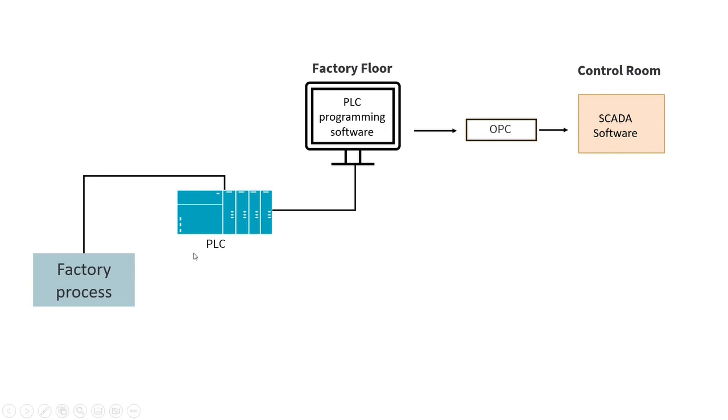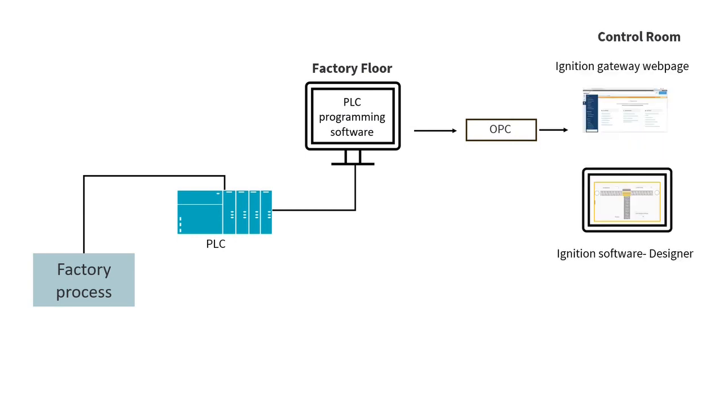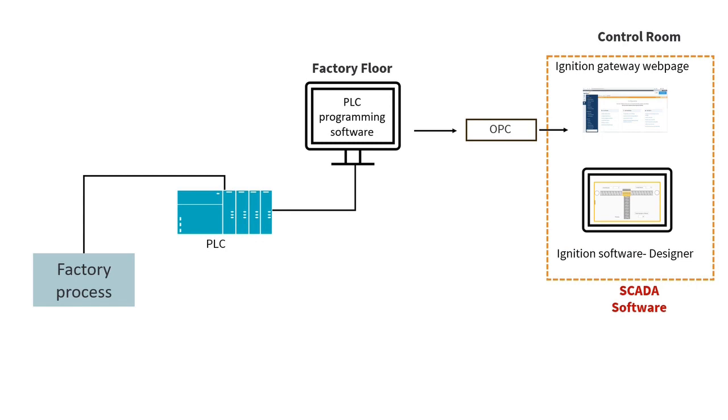So first you have a factory process. It could be any process, like for example, sorting boxes on a conveyor belt or mixing a liquid in a tank. And then you have a PLC that regulates the movement of the process. And then you have a PLC programming software for that PLC. Now in order to transfer data to a SCADA software, we have an OPC server that takes the data from the PLC all the way to our SCADA software. So for this example, I would use Ignition software here at this step over here, right at the end. So I have Ignition Gateway web page and Ignition Designer. Both of them are SCADA software.